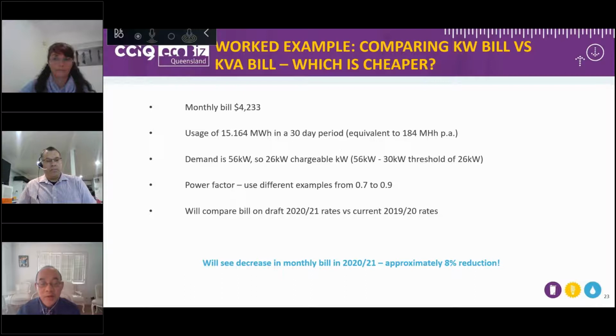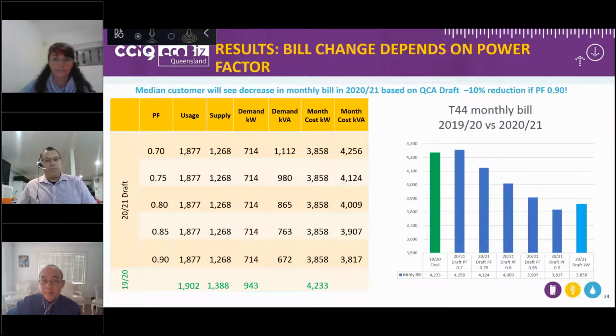What I also do in this calculation is use different power factors from 0.7 to 0.9 to see what the impact is going on to kVA tariffs. And in order to do this, I will compare the draft 2020-21 rates which were released by the QCA, and compare it with the current rates that you're paying for 2019-20. So what you can see here, and I'll just walk through the graph on the right, is the different scenarios based on whether you're staying on kilowatt charging as well as kVA charging. So currently on the green bar, you can see on the current pricing for 2019-20, you're paying $4,233. We are seeing a reduction in the network costs.